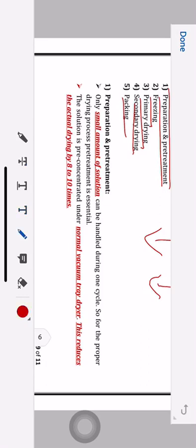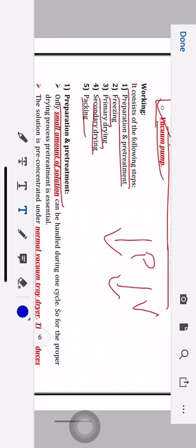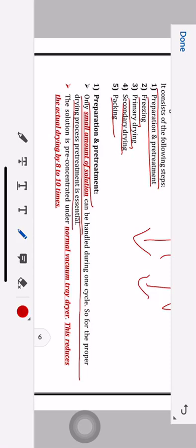First step — preparation and pre-treatment. Pre-treatment is essential because in the freeze dryer, only a small amount of sample can be processed at one time, so you need to reduce the bulk of your product. Only a small amount of solution can be handled during one cycle. The solution is pre-concentrated under a normal vacuum tray dryer. This reduces the actual drying time by 8 to 10 times.